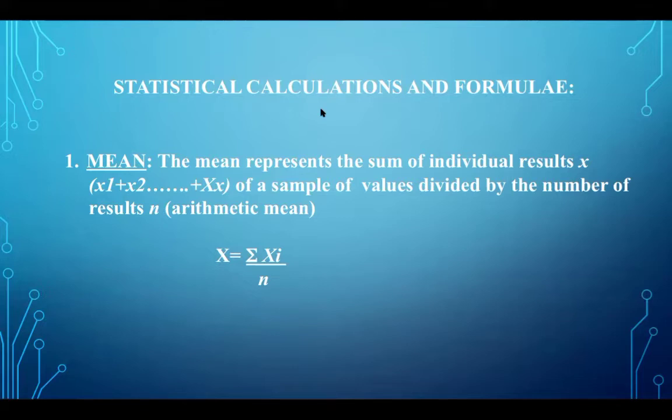Yes, excellent. See, this you are defining in your lab, your laboratory conditions are different. Your environmental condition of the lab is different. Your wear and tear of the machine is different. Your reagent storage is different. Quality of your reagent is different. Your calibrator storage, control storage, water quality, competence of the observer. There are so many variables which can affect a result, right? So you have to calculate the mean in your laboratory.